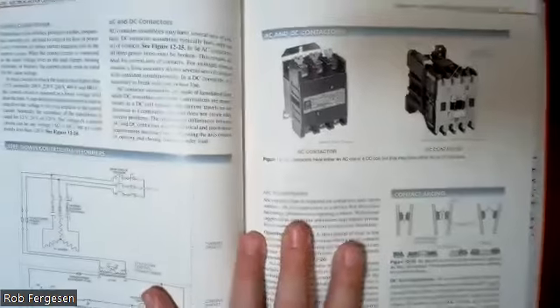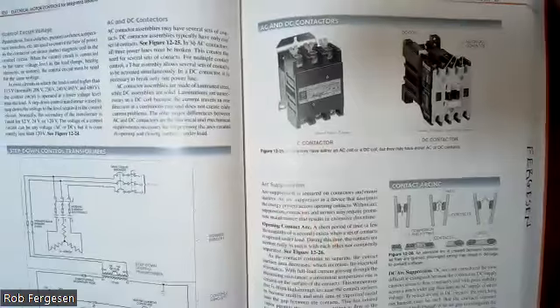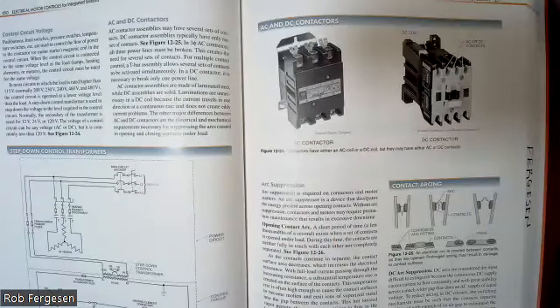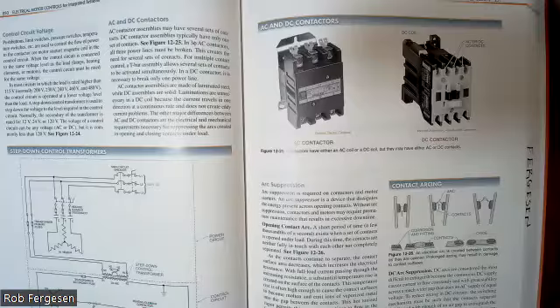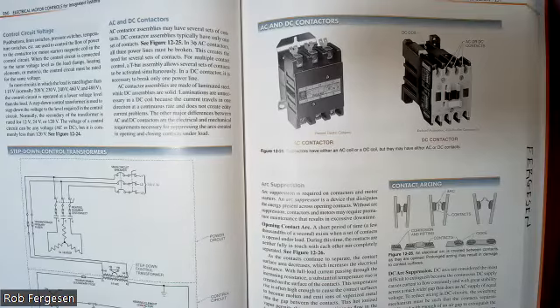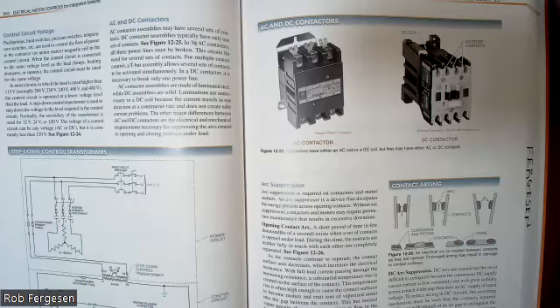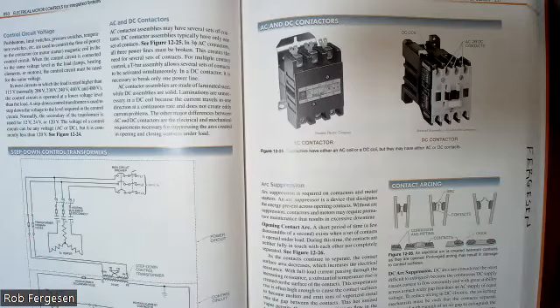So the book takes you through a couple different types of circuits. A lot of contactors in the US are AC, but more and more we're seeing the DC contactors becoming common, especially in pieces of equipment coming out of Europe. So AC is pretty typical, but more and more you're going to see DC control voltage. So you're going to have a little DC power supply instead of an AC transformer providing you your control power.